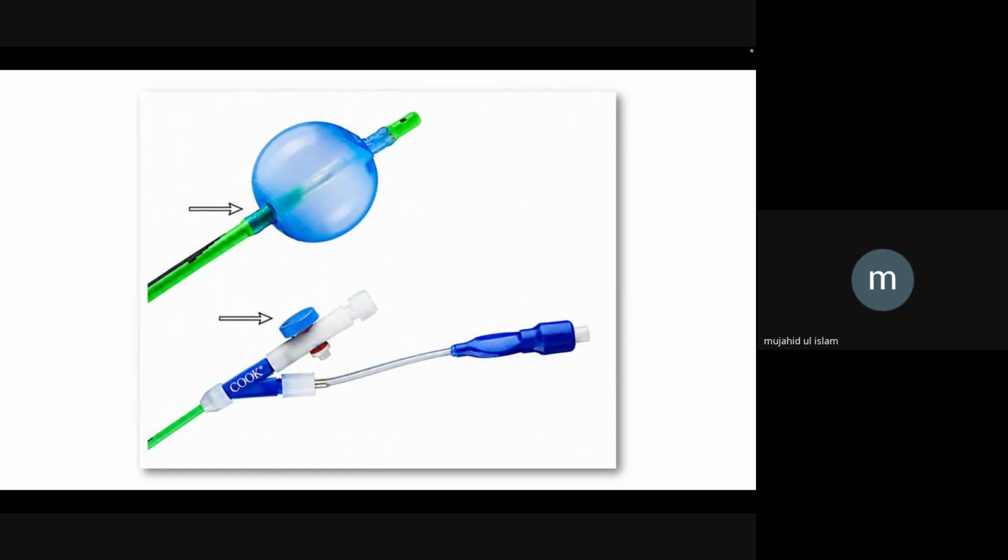The Cohen bronchial blocker differs from the Arndt blocker by using a rotating control wheel rather than a wire loop. Turning the proximal wheel deflects the distal tip, allowing precise steering into the target bronchus under fiber optic bronchoscopic guidance.